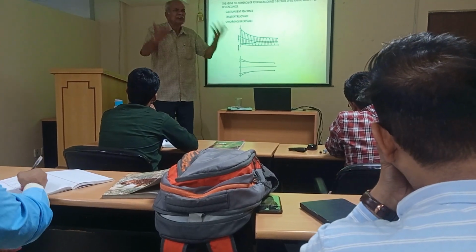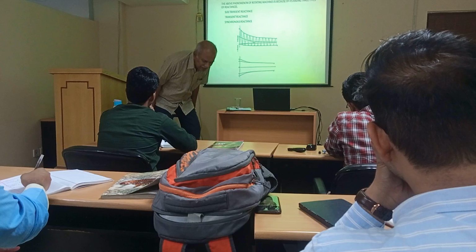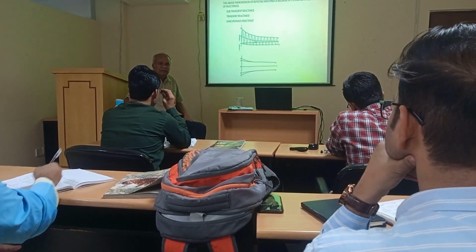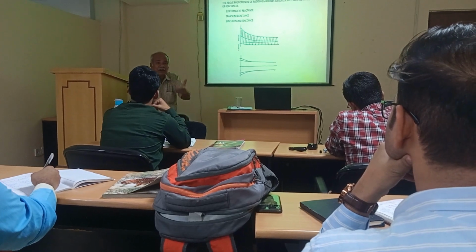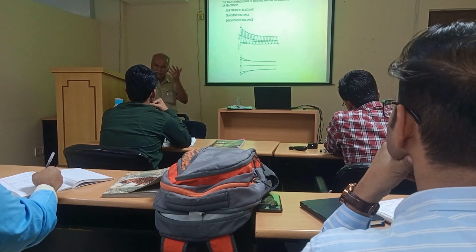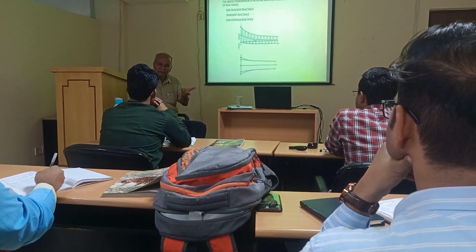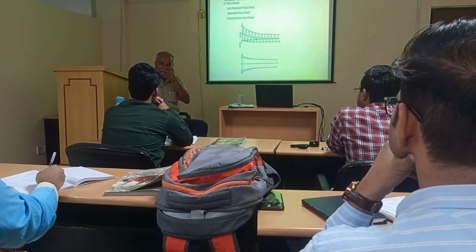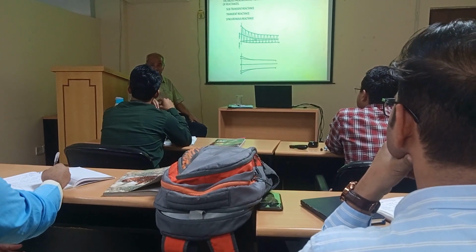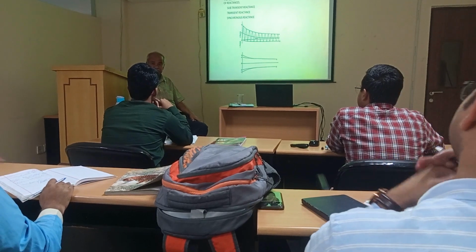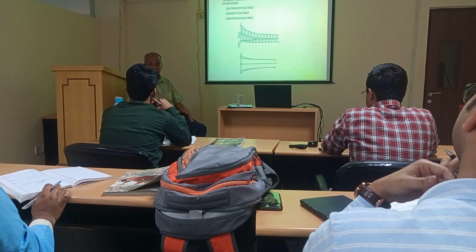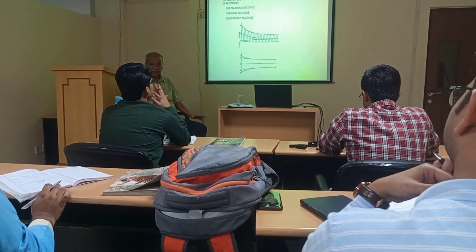For a transformer winding, you do the no load loss and load loss tests, then you find out how much is the reactance. Generally it is also like this: voltage by current. To calculate reactance, we have to consider the RMS value of the voltage, definitely not the peak value. That is the reason divided by root 2 is coming. Am I clear to you all on this?